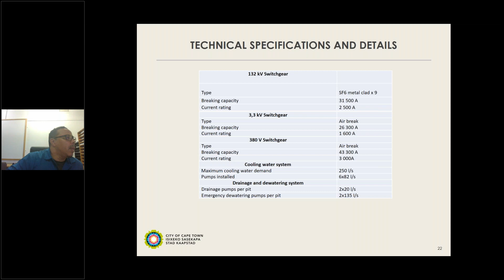I wanted to put this here. I know you can't see it well, but I wanted to give you a feel for the size and complexity of the electrical network at the power station. As I said, we generate at 12 kV and step up to 132, but we don't have a 12 kV bus here. We've got a dual 132 kV bus, a 3.3 kV bus, and also a quite extensive 380 volt bus.